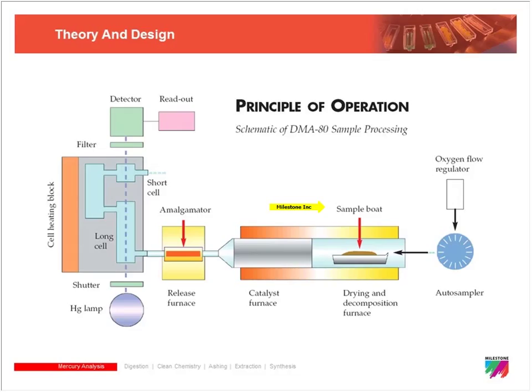The carrier gas moves the mercury from the catalyst chamber onto a gold amalgamator cell. So the mercury is collected during the entire decomposition process, and once the decomposition process is completely finished, the software sends a signal to the amalgamator where it flash heats to over 800 C, simultaneously releasing all of the mercury from the sample as it enters into the spectrophotometer cell. In the cell itself, the mercury passes through two detection cells where we have a dedicated mercury lamp that is tuned to a specific wavelength for mercury. The height peaks are detected by the system, and a readout is sent to the terminal so you can determine what level of mercury passed through the detector cell.